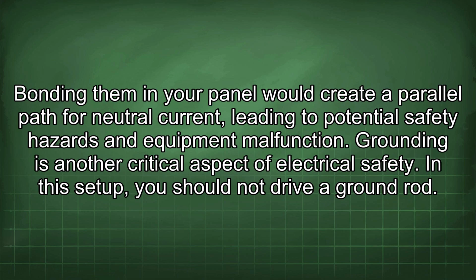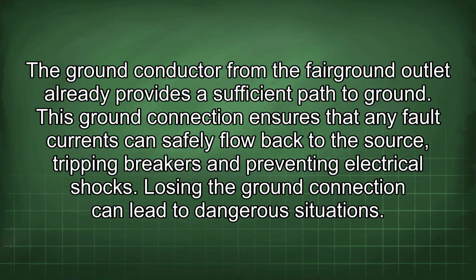In this setup, you should not drive a ground rod. The ground conductor from the Fairground outlet already provides a sufficient path to ground. This ground connection ensures that any fault currents can safely flow back to the source, tripping breakers and preventing electrical shocks. Losing the ground connection can lead to dangerous situations.